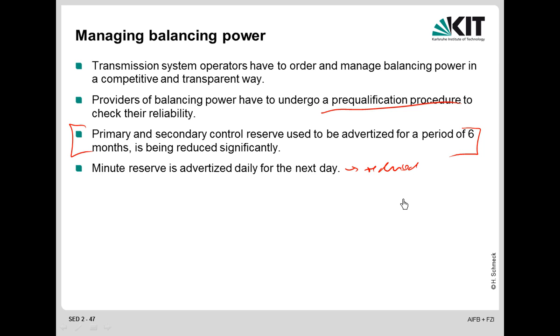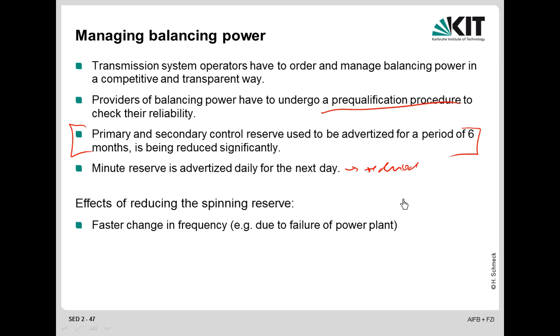Reduced to an intraday auction, the effect of reducing the spinning reserve is that you have a faster change in frequency. The momentary reserve is no longer there as it used to be, so the dynamics of the frequency are much higher. This means it requires a faster response of primary control, because primary control's job is just to stop the frequency deviation and return it towards 50 hertz, while actual stabilization is guaranteed by secondary control power. Primary control's main purpose is to stop and slightly reduce the deviation, but it cannot stabilize it in the long run.